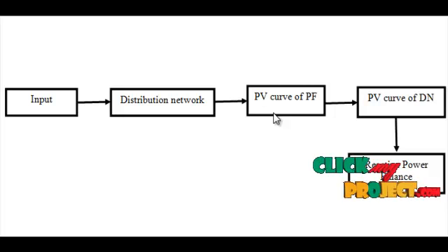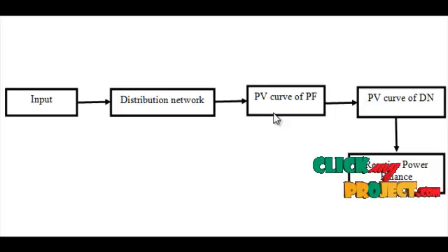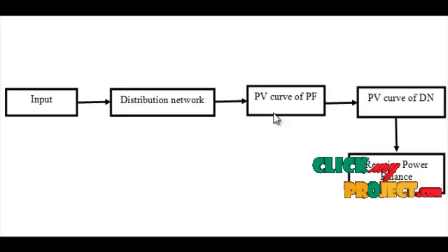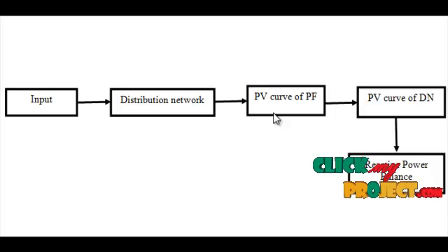It will not only lead to lower voltage quality and increased grid loss, but also reduce the grid transmission power. The PV curve is drawn with KQP3 equal to 0.2, 0.4, 0.6, 0.8 respectively. The ratio of reactive with respect to active power increases due to decreased power factor. The maximum power transmitted from the grid to bus 3 is reduced. KQP3 is the ratio of Q3 with respect to P3.